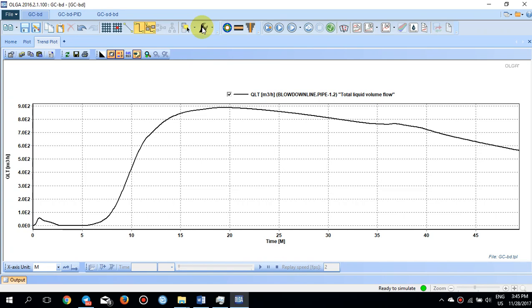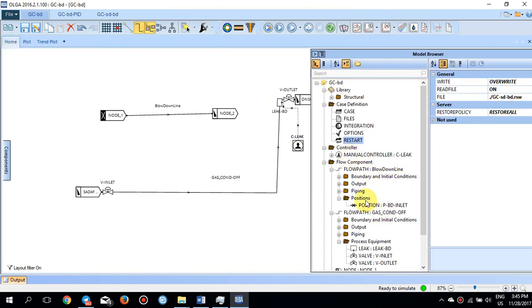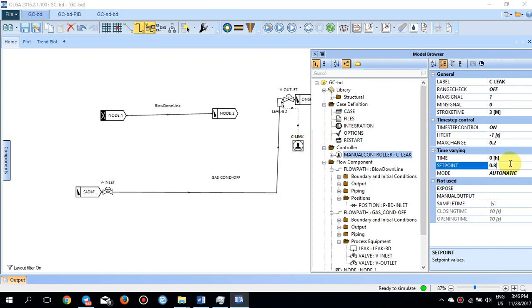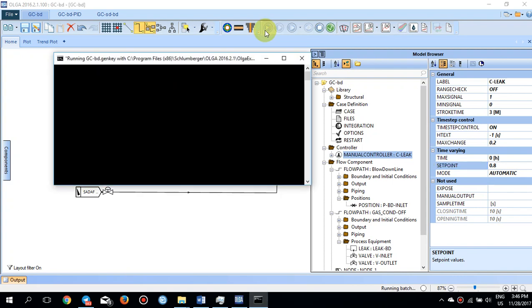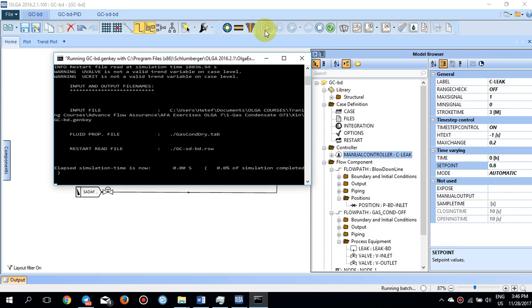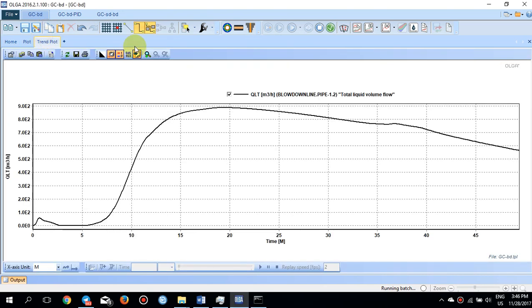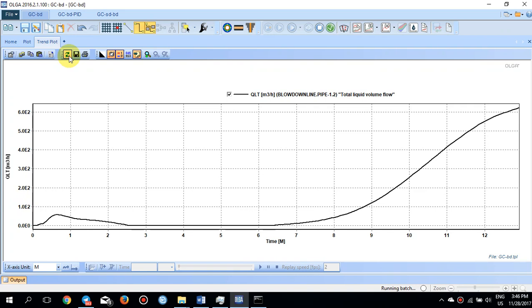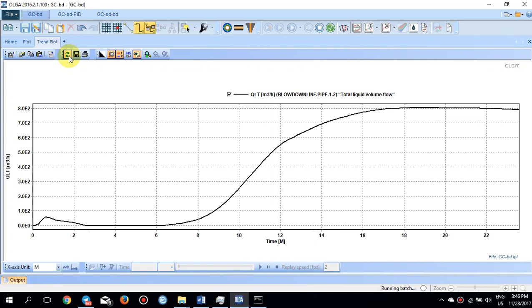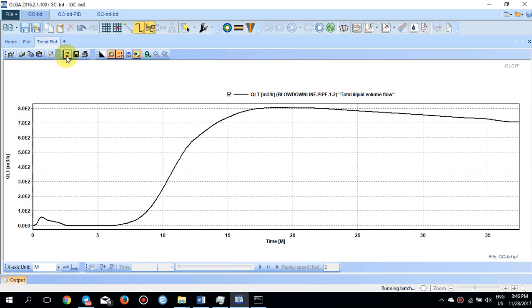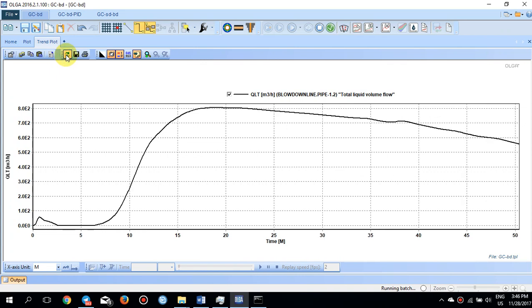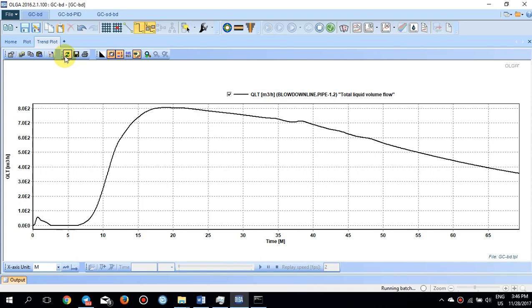I go back to the controller and set the set point to 80% and run it again. The liquid contents come into the blowdown line, and after about 20 minutes it reaches its maximum of 800 cubic meters per hour without exceeding that value significantly. Then it starts to decrease again as the liquid contents are blown down from both the blowdown line and the gas condensate line.